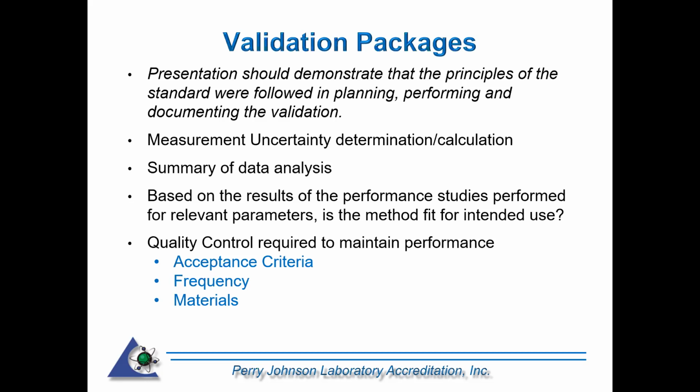So make sure that if you're doing a quantitative method, that the measurement uncertainty has been determined. If it's going to be reported as a pass or fail, or acceptable, unacceptable, make sure that you have a decision rule associated with how the measurement uncertainty is applied to make that conforming statement. I could do 5 webinars on measurement uncertainty, so I'm going to move on from it at this point and talk about summarizing your data analysis.